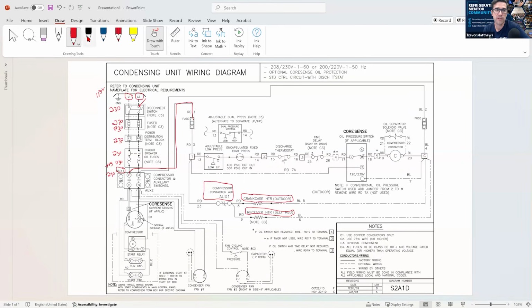And then now we have L2. We'll go across like this and we'll go up. This is our L2, and I'm just showing you as we go around. Just for those that are listening, I'm just highlighting it to fuse 2. Okay, so now, well, what do we want to check? So let's check if we got power here. On the upstream side of the fuse, we should have 230. On the downstream side, we should still have 230 because that lead is still in L2. So I should get 230 here. If I go down to this terminal block, I should get 230 there. And then if I go on this side, I should have 230 here.